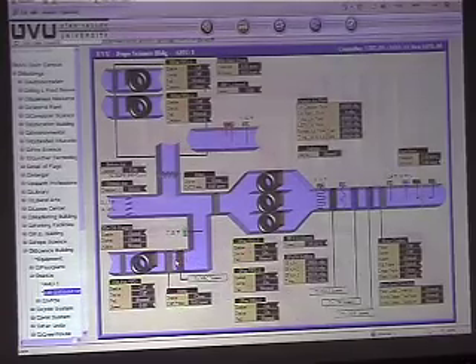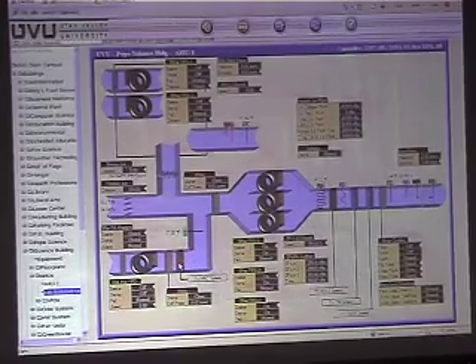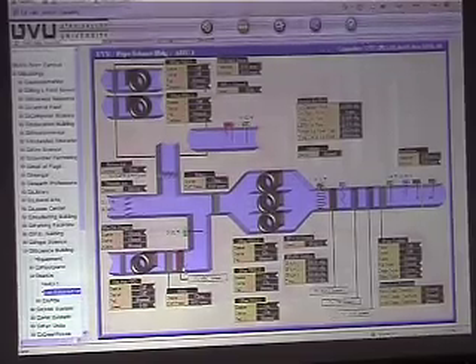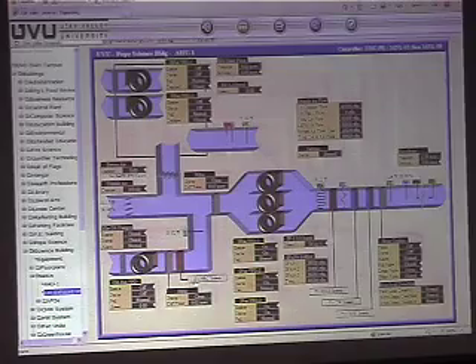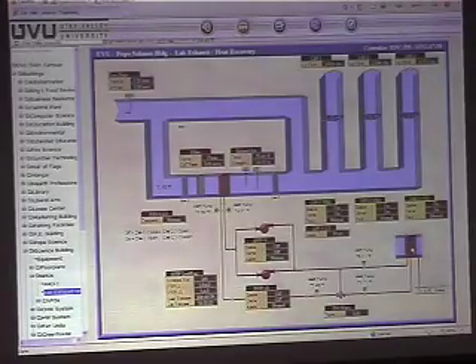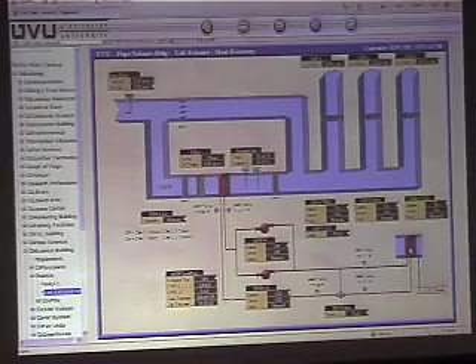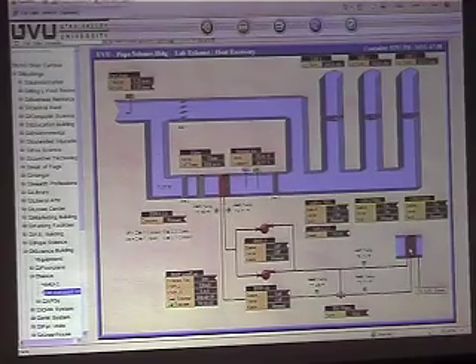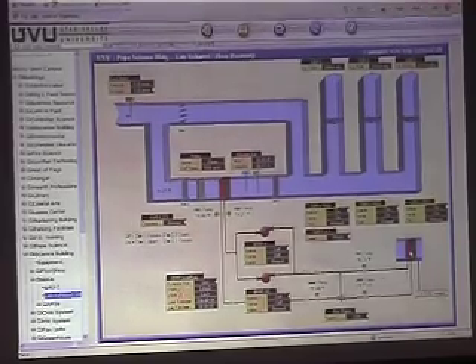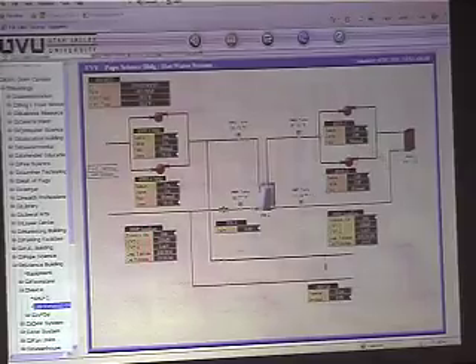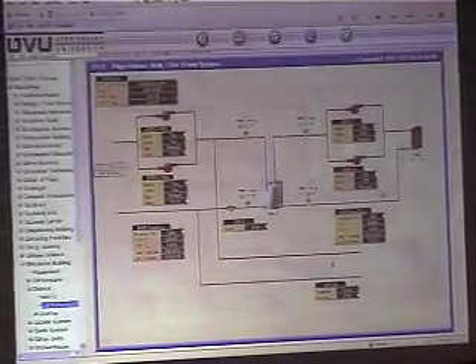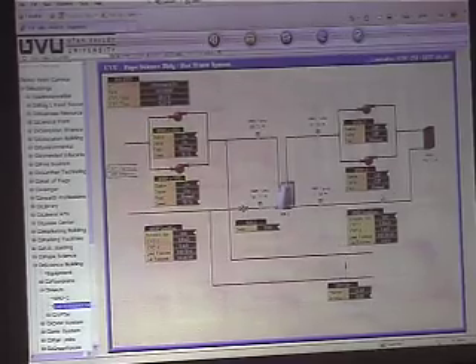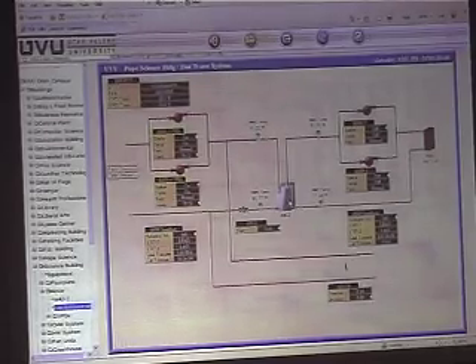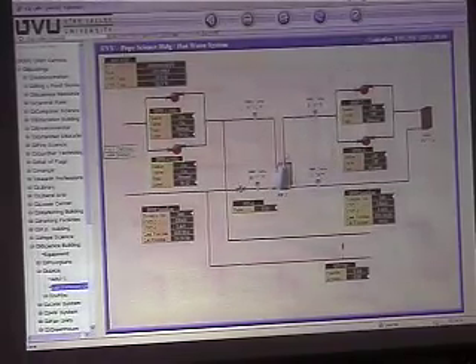Yeah, one other question, you can go back on the back screen. On that coil down right there, what's that coil tied to? Is that to our building water? That's your heat recovery. So if you click on this, it takes you to that one right there. Okay, and is that the glycol loop? I'm pretty sure they have glycol in that one. But there's also the glycol loop that's this one right here. Right. And that's this loop right here on this heat exchanger. I didn't know if that other coil was tied into the glycol loop or the building water. Yeah, this one's your building water, and then you've got the heat exchanger isolating it. So you've got your glycol in this loop here.